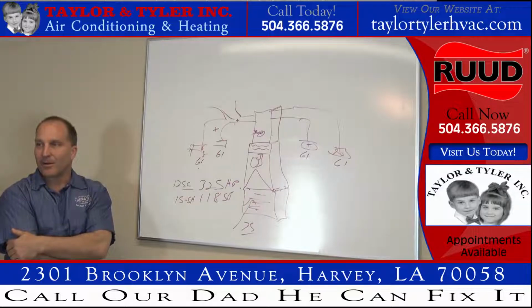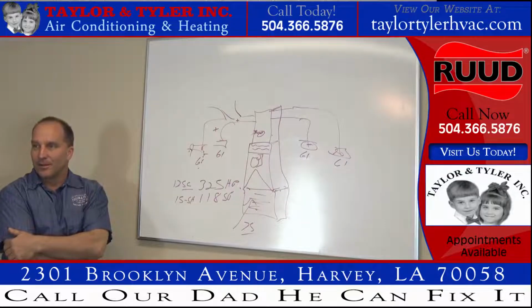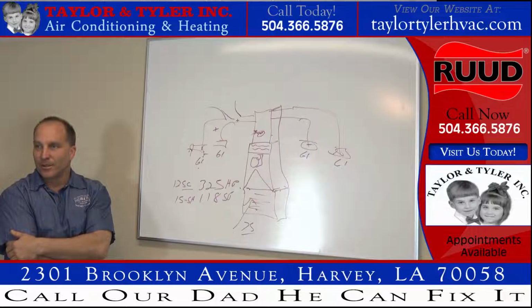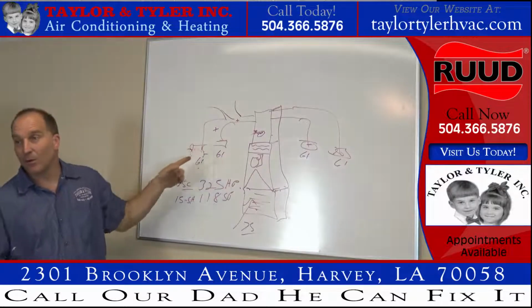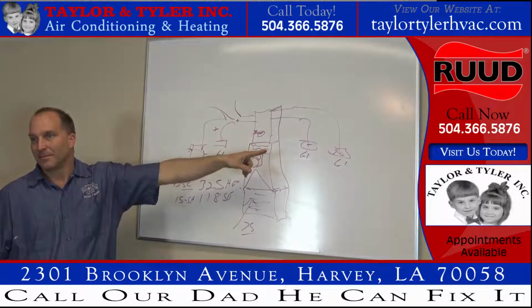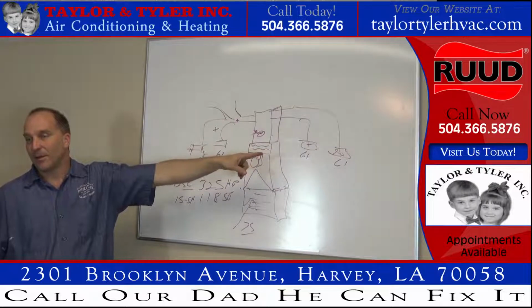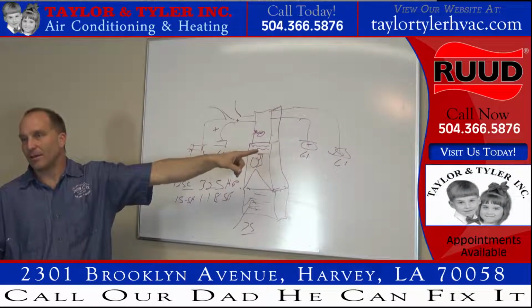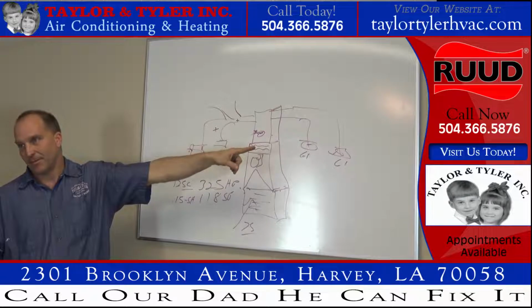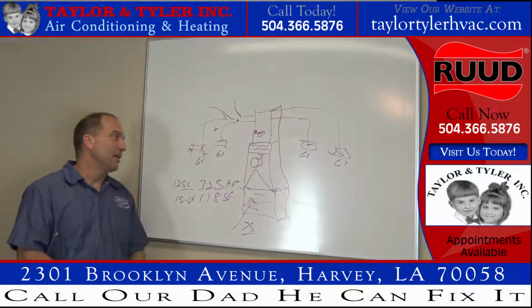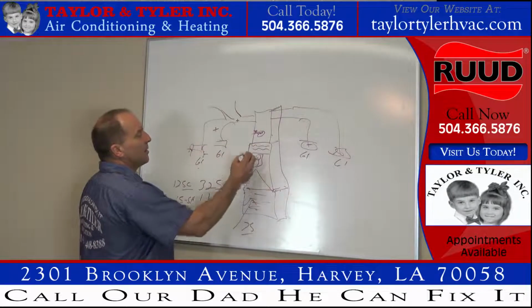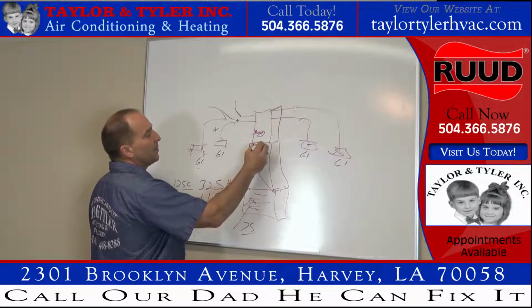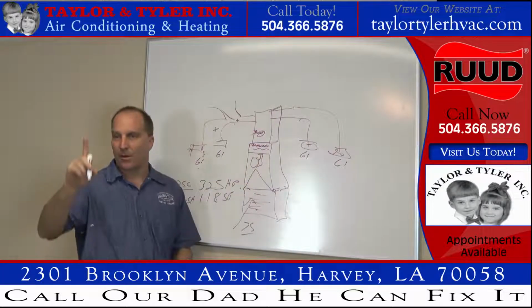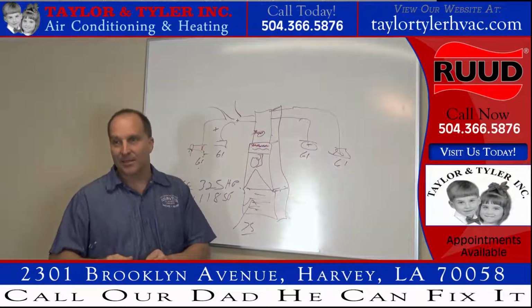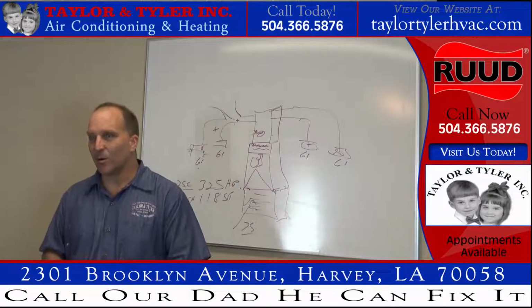So I don't have to call another technician? No. Why don't I have to call another technician? Because my delta T gave it away. The 3 technicians before never checked the delta T. So what happens is, this heating element is heating up, this one's not. I got one 5 kW heat system, and let me tell you what gave it away.